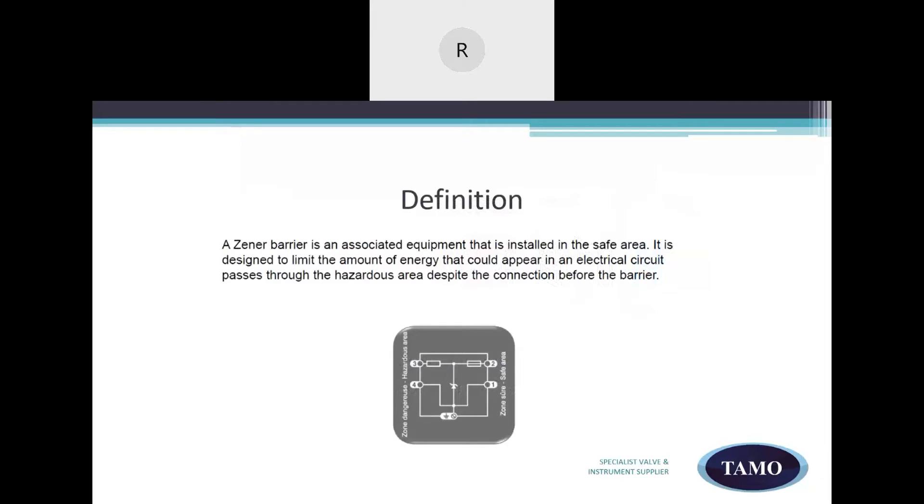Let's look at the definition of a Zener barrier. It's an associated device or equipment that is installed in the safe area. It is designed to limit the amount of energy that could appear in an electrical circuit passing through the hazardous area. As with any intrinsic safety equipment, the Zener barrier allows cables to short circuit to each other or to metallic parts connected to ground without any danger.